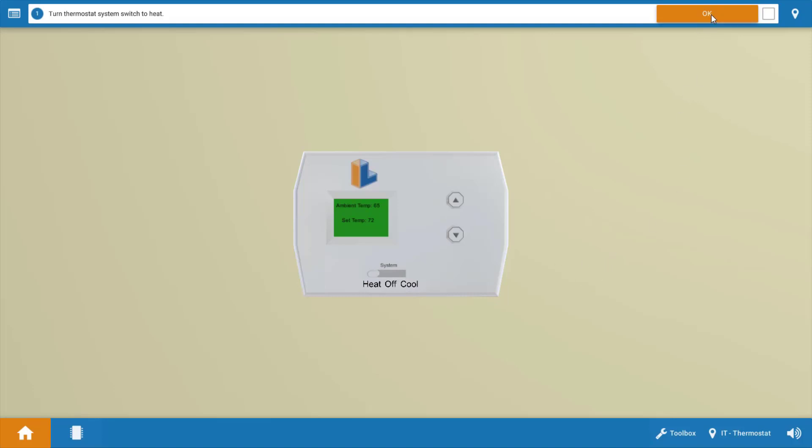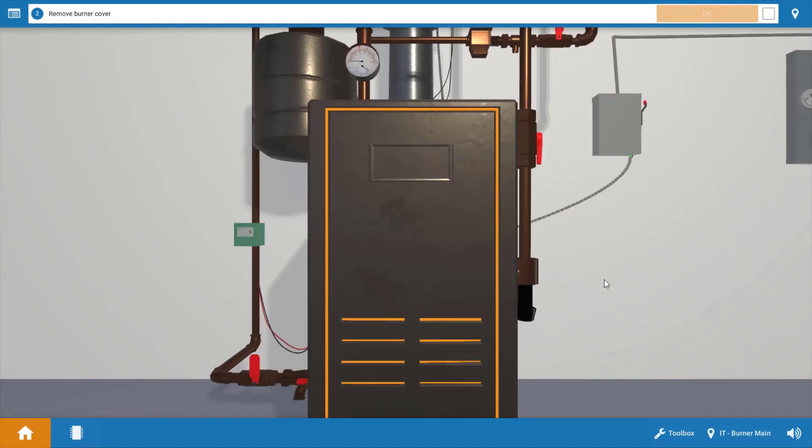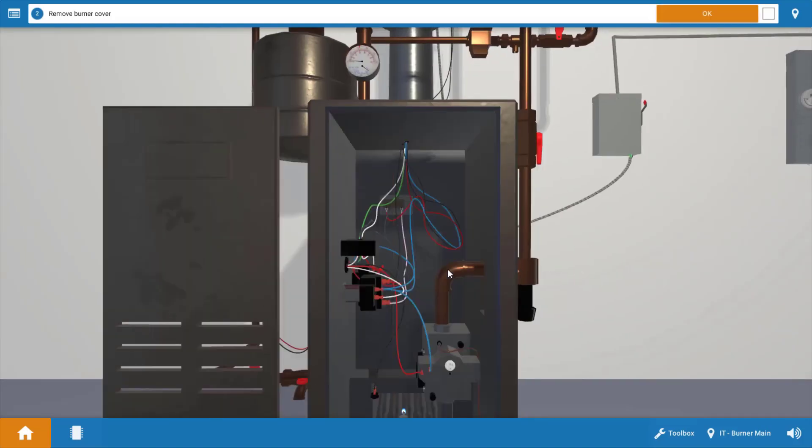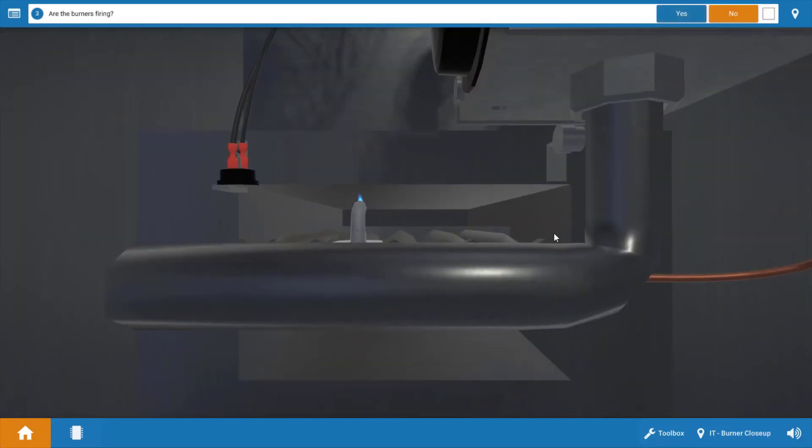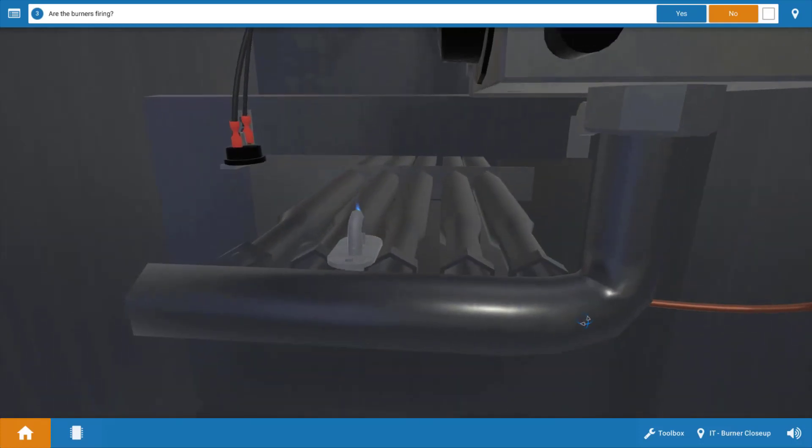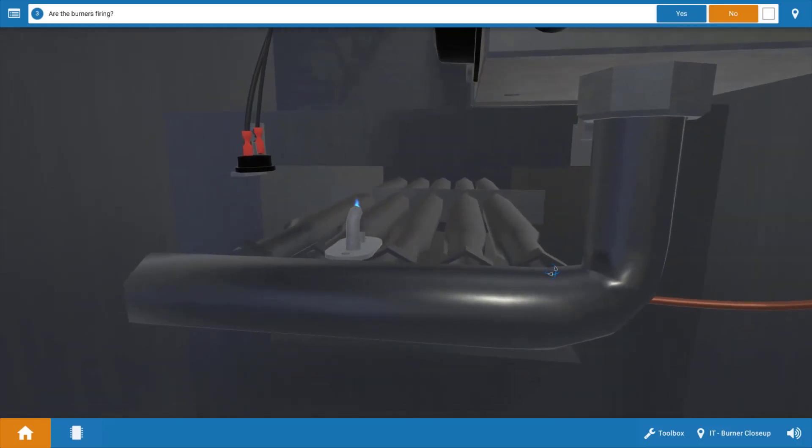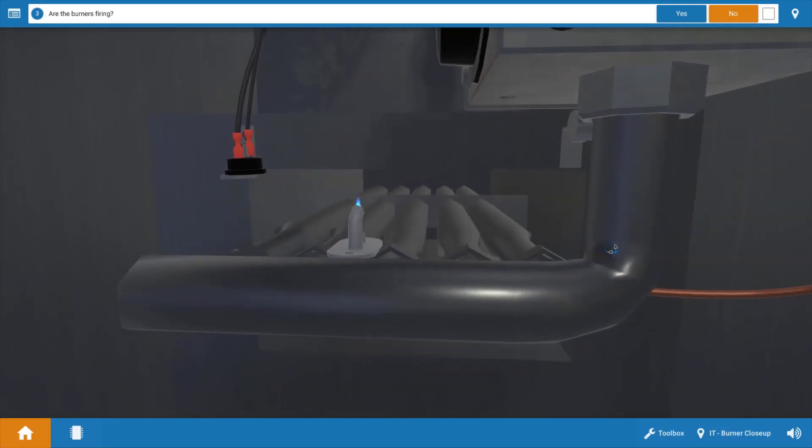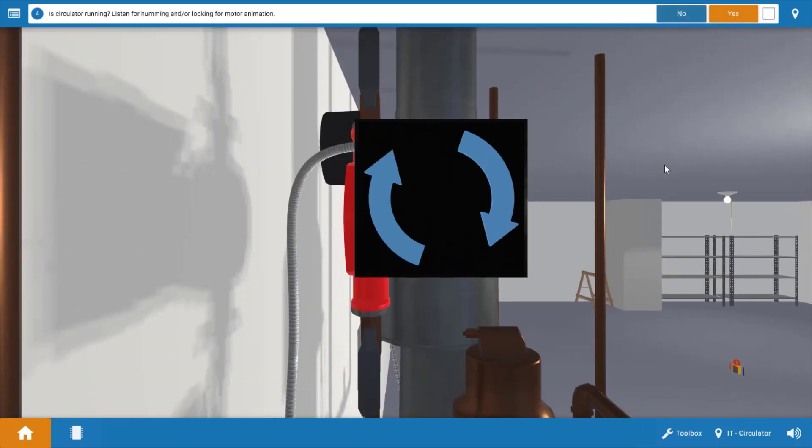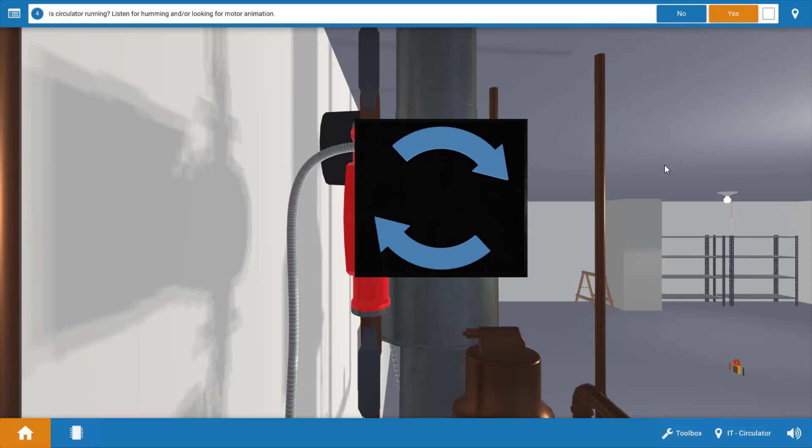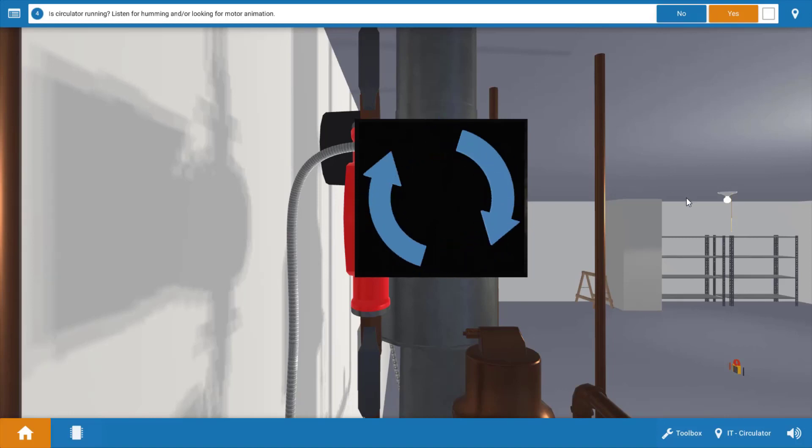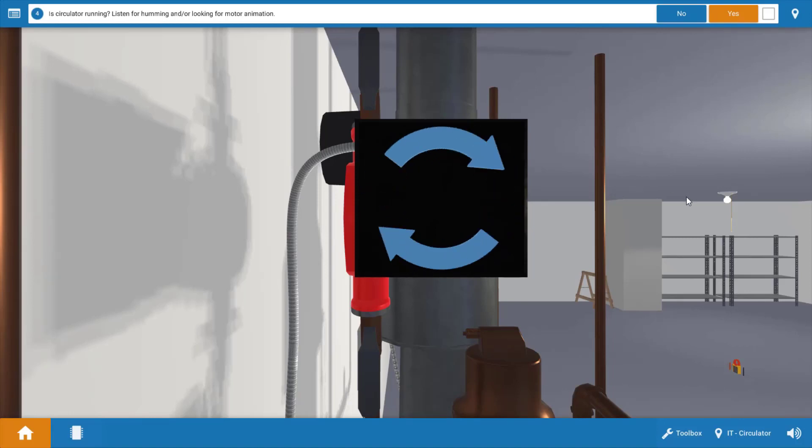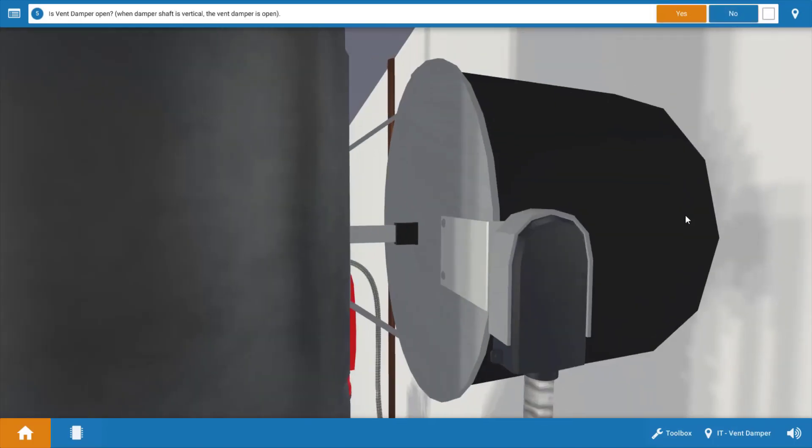Next click OK in the procedure guide and we're going to need to refer to this after each step. Next we're going to remove the cover from the boiler and do a brief inspection of what's running. Now that we've done this click OK and our next step is to see if the burners are firing. If we look we can see the burners are not firing, although we do have a pilot flame so we don't have a thermocouple issue. Our circulator pump however is in fact running as evidenced by these spinning blue arrows.